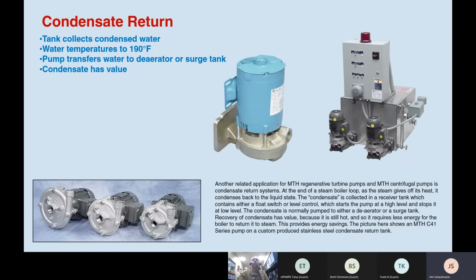Right. So, condensate return: after the boiler system in the building or house has been used up, and all that steam has been turned back into water, it goes into a special holding tank. Our pump gets used to move that water either back into the boiler, which needs the high pressure pump, or back into the boiler feed tank, for which you can use a centrifugal pump.